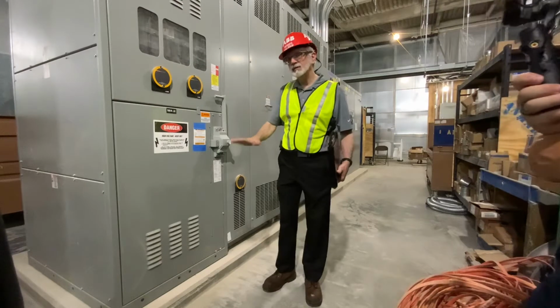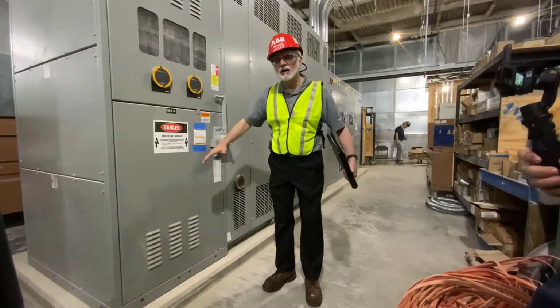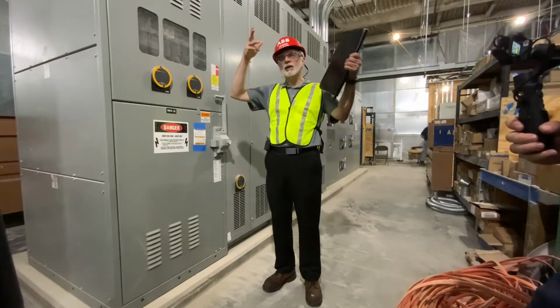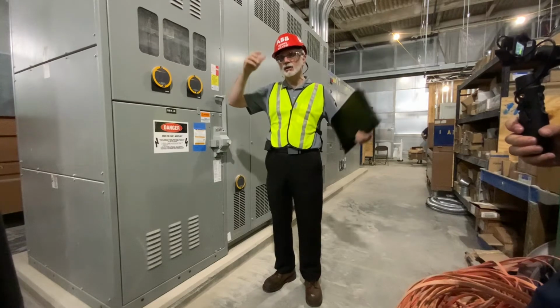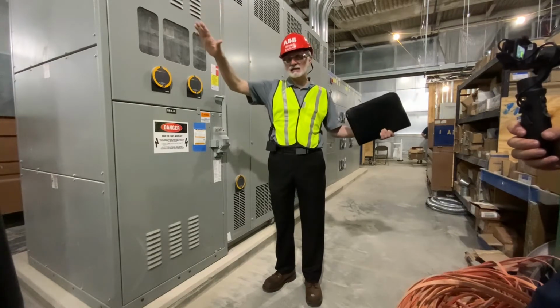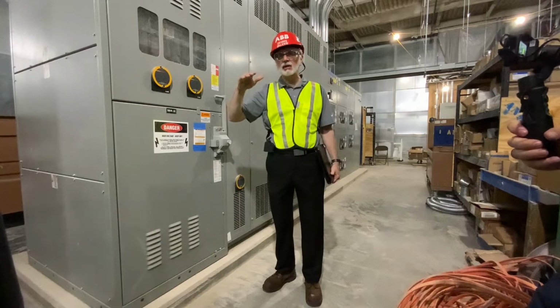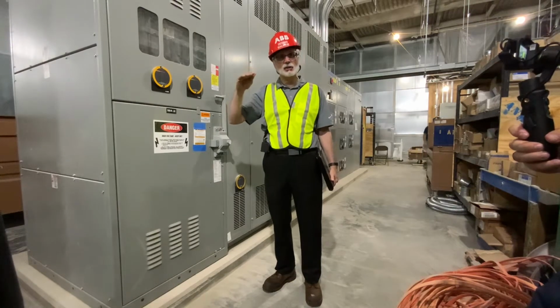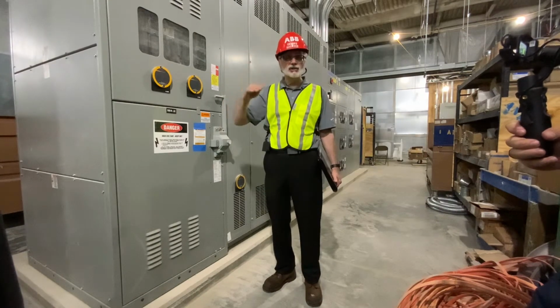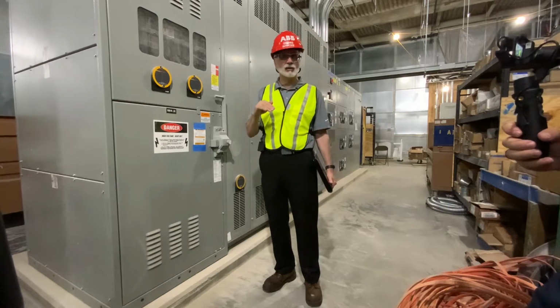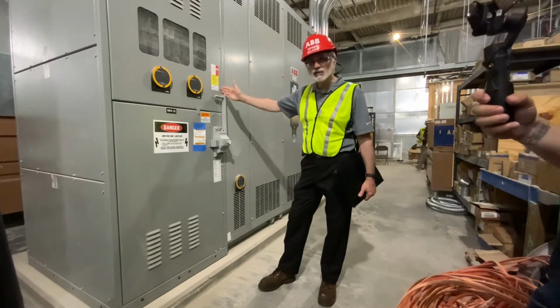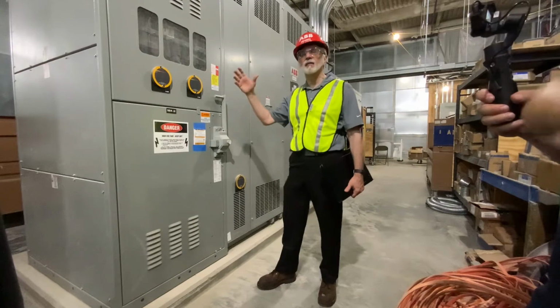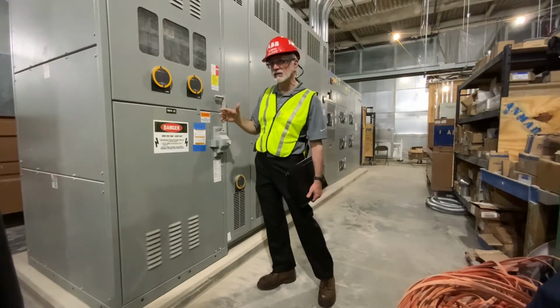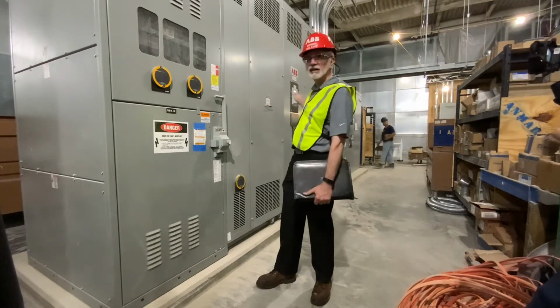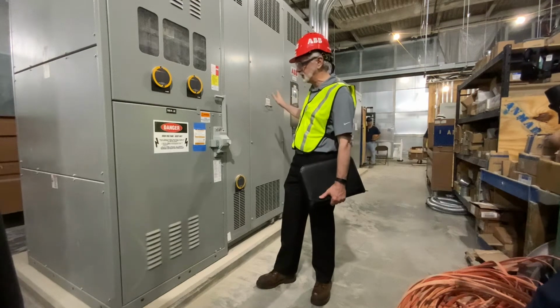As we talked about from down below, you have a feeder that's coming up from the main incoming service and is landing in this area here. So we're stepping the equipment down from 13,200 volts down to a usable 277/480 volts. This is the main switch that's coming up from one side of the unit substation. This is the local means of disconnect for the substation.